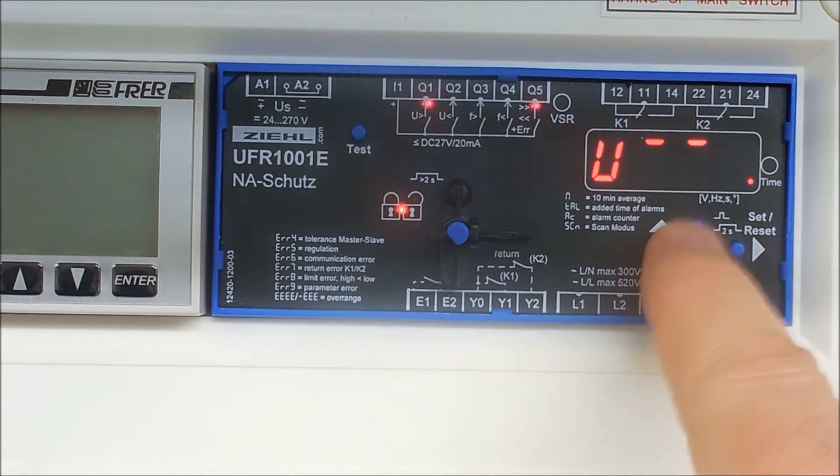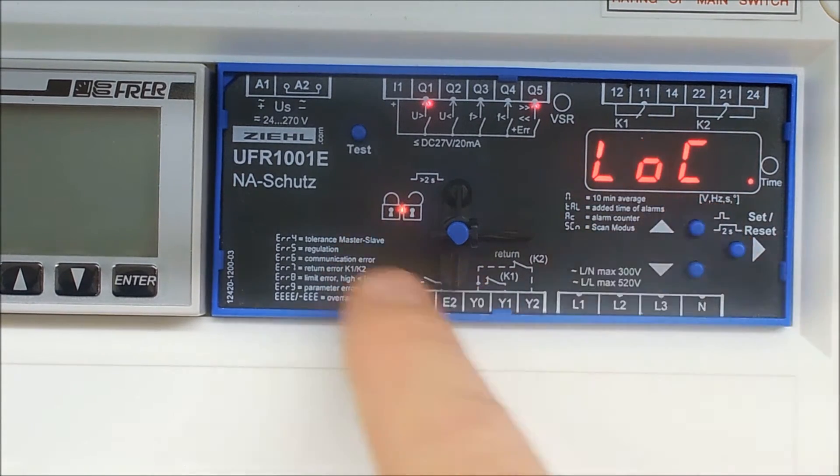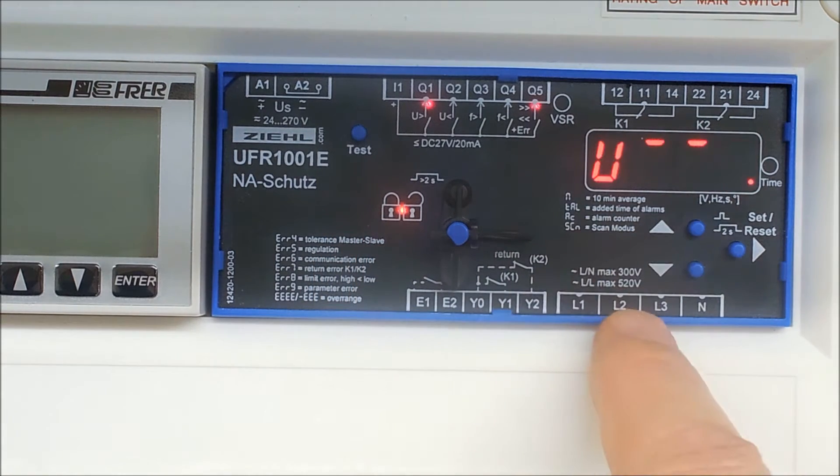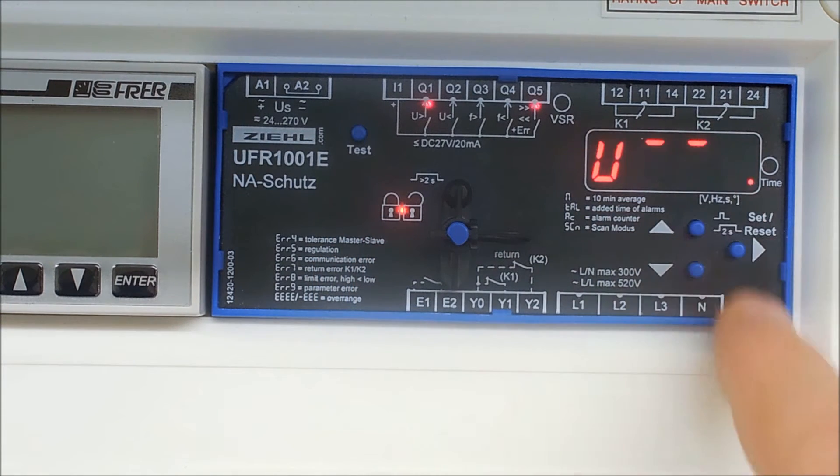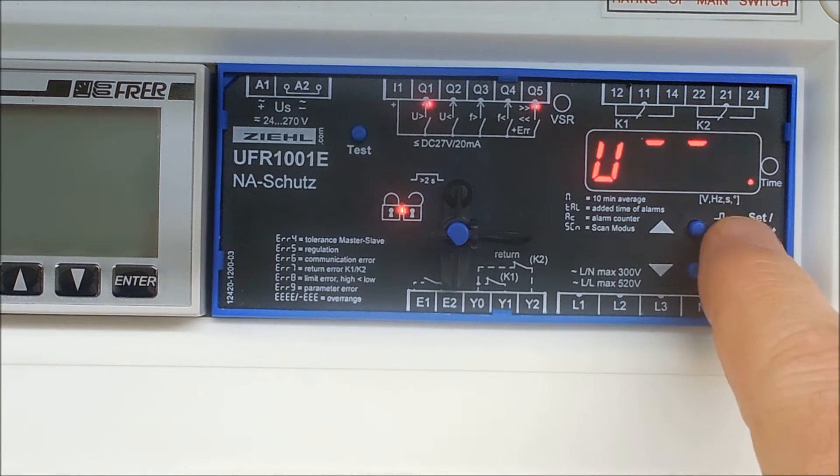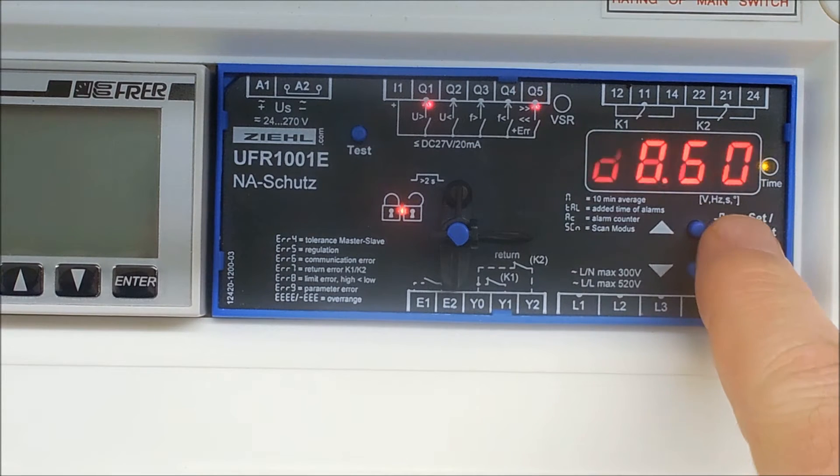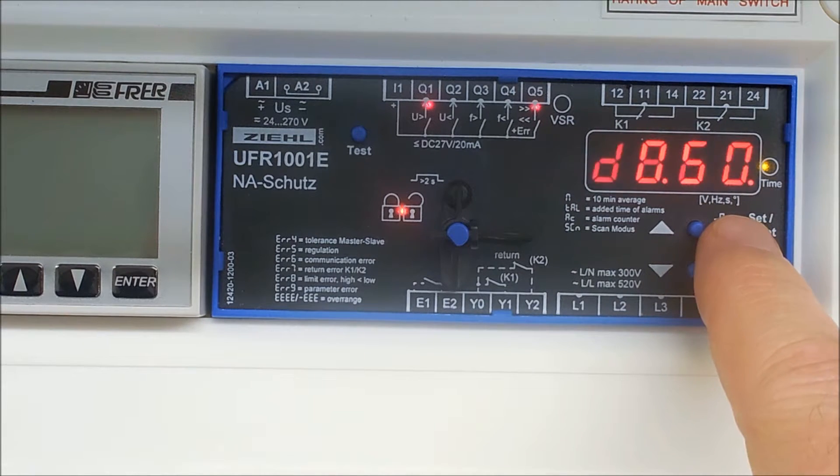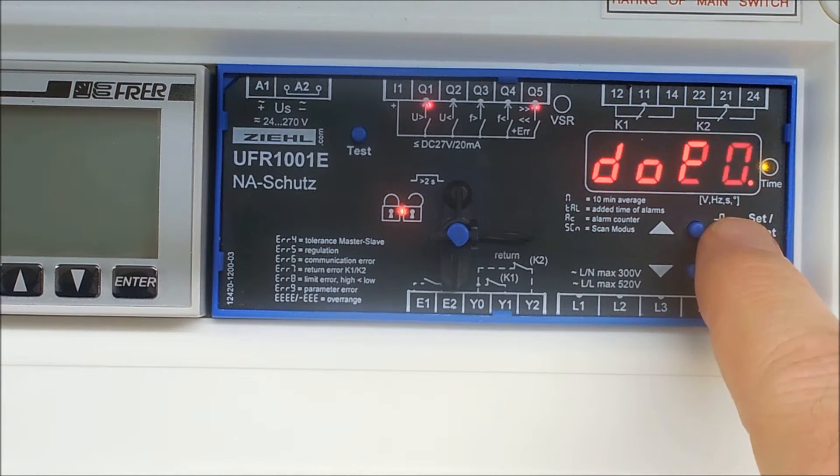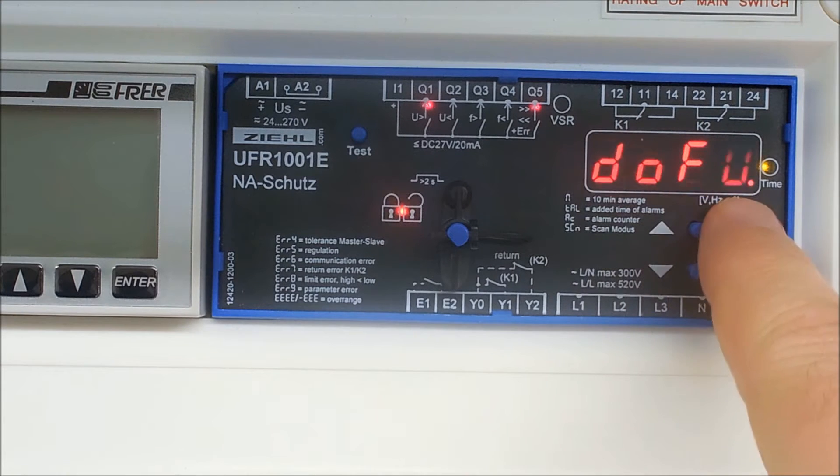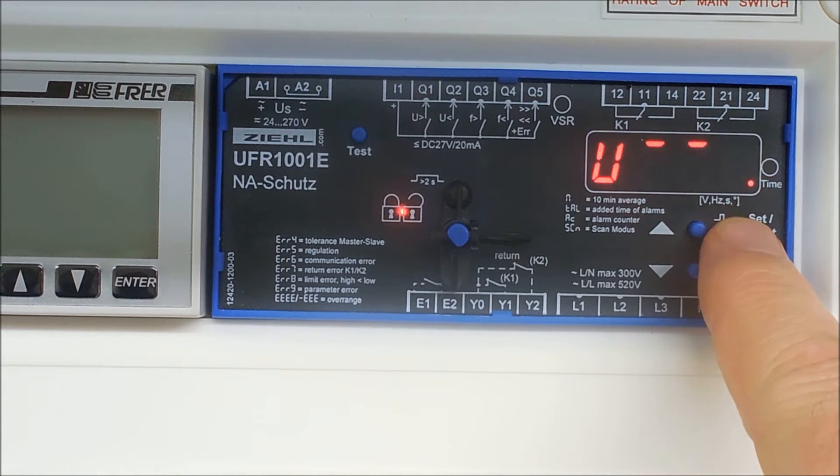I will show you again. Press the up key, LED flashes to indicate the system is locked out. If you continue over to the right you can see the hysteresis. You have the delay which is half a second and then you have the delay off before it will reset of 20 seconds.